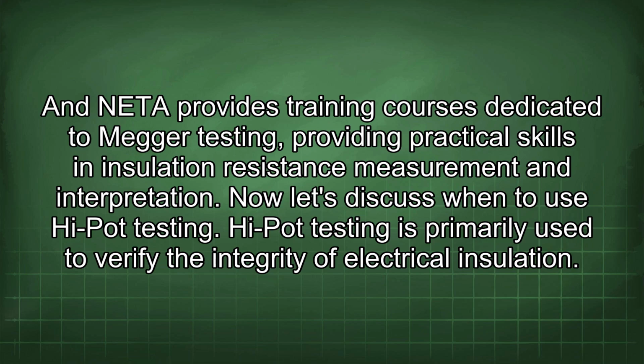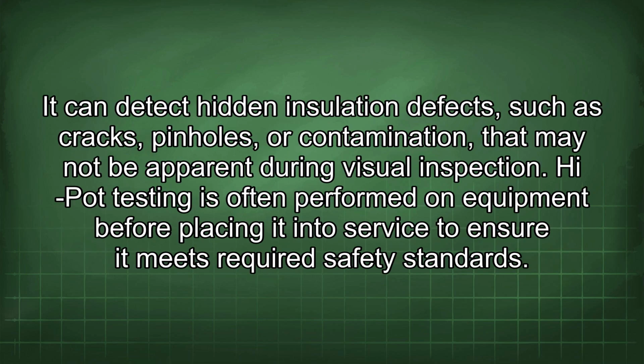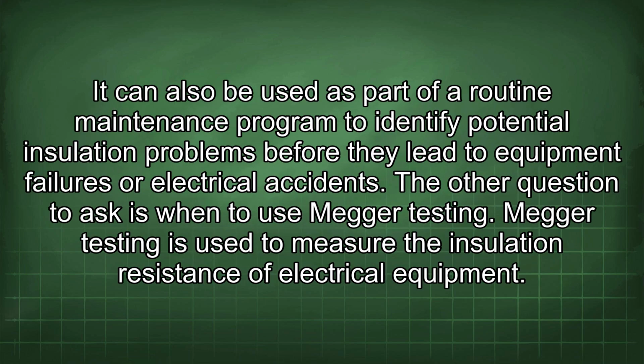Now let's discuss when to use high pot testing. High pot testing is primarily used to verify the integrity of electrical insulation. It can detect hidden insulation defects such as cracks, pinholes, or contamination that may not be apparent during visual inspection. High pot testing is often performed on equipment before placing it into service to ensure it meets required safety standards. It can also be used as part of a routine maintenance program to identify potential insulation problems before they lead to equipment failures or electrical accidents.